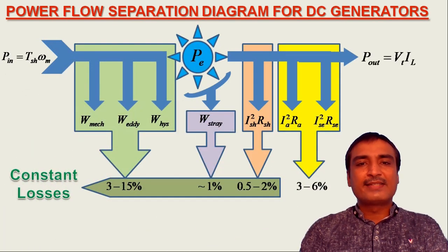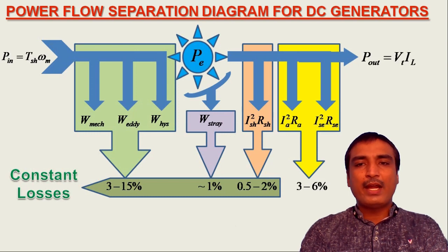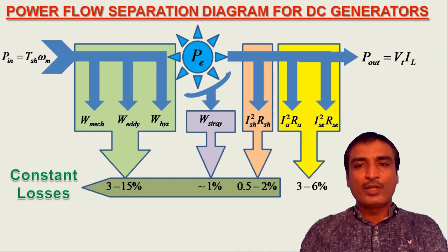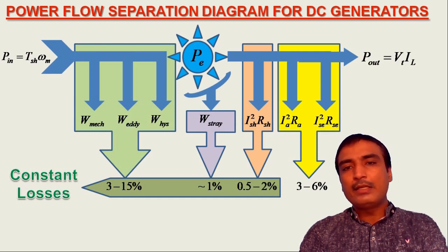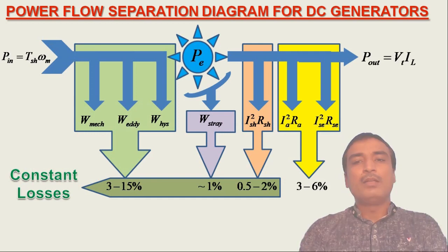On the other hand, the series field winding copper loss and the armature circuit copper losses — including interpole winding copper loss, compensating winding copper loss and brush contact loss — increase as the load on the DC generator is increased. These losses together are called variable losses.